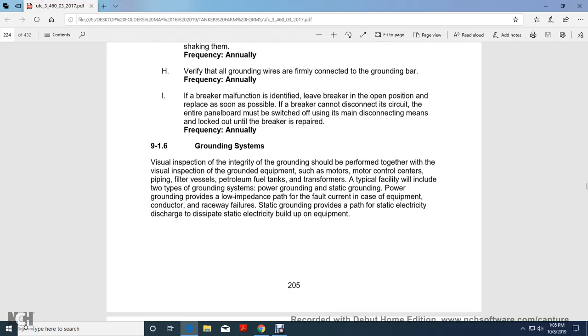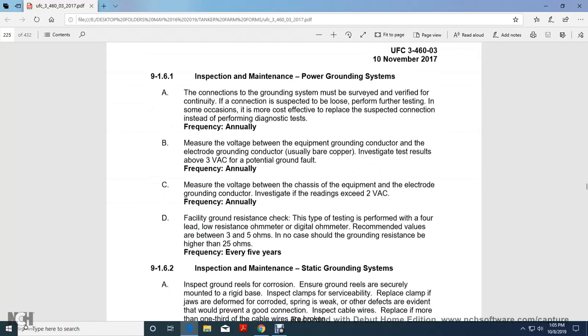Typically, facilities include two types of grounding system: power grounding and static grounding. Power grounding provides a low impedance path for the fault current in case of equipment, conductor, and raceway failures. The static grounding provides a path for static electricity to discharge and dissipate static electricity from the equipment. Inspection and maintenance of the power grounding system.